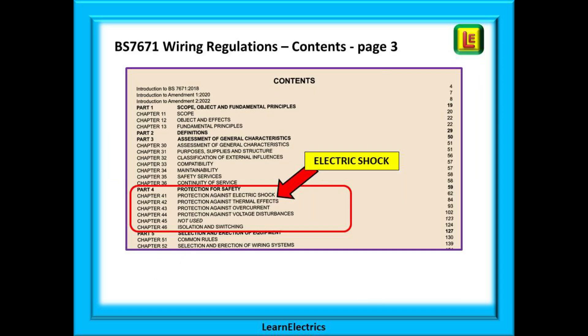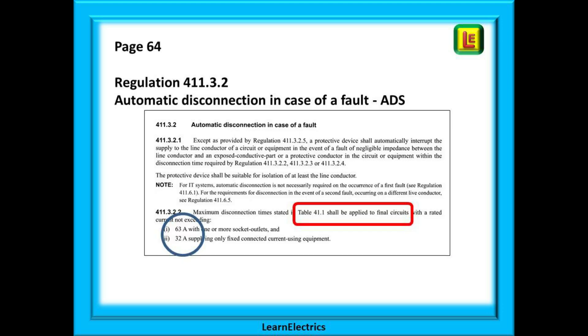If we look at page 3, the contents page of the wiring regulations book, we will find part 4, and this is all about protection for safety. Below this heading is chapter 41, protection against electric shock, and this is where we will find information about ZS and disconnection times. If we turn to chapter 41 and go to page 64, we will find Regulation 411.3.2. This is our starting point. It is titled Automatic Disconnection in Case of Fault. This is what we shorten to ADS, Automatic Disconnection of Supply. In other words, if a fault occurs, the fuse or breaker will automatically disconnect the supply and make the circuit safe.